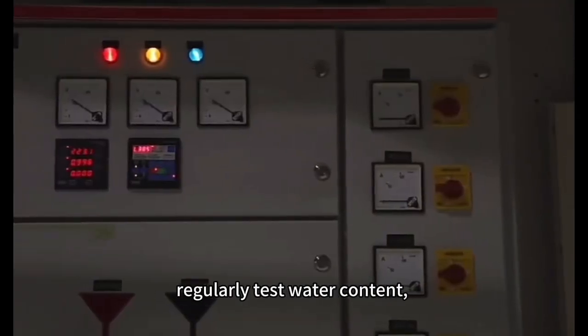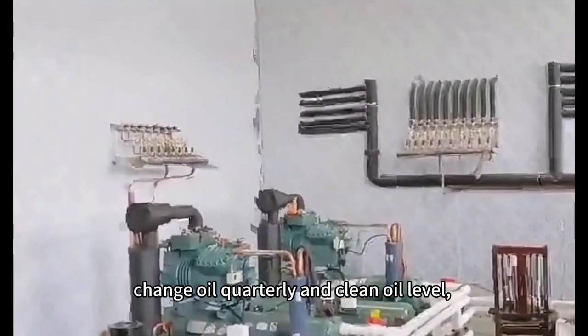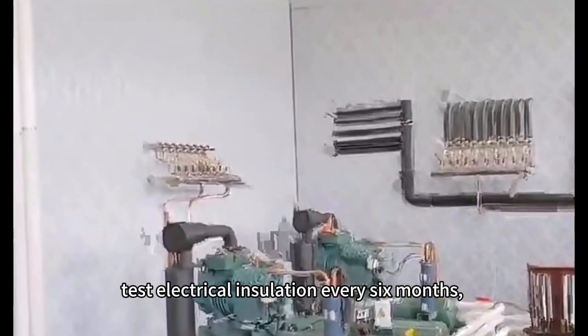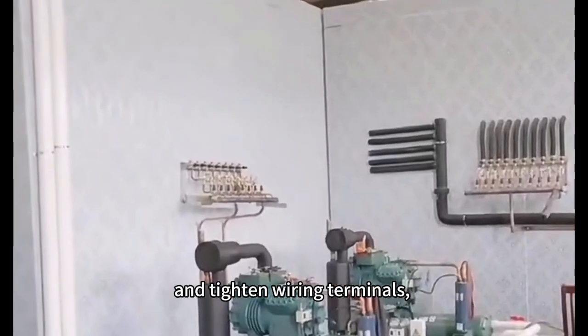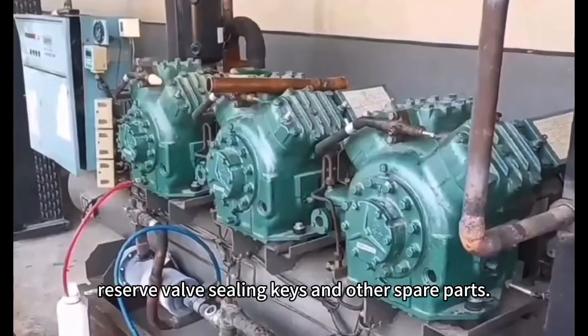Regularly test water content. Change oil quarterly and check the oil level. Test electrical insulation every 6 months, and tighten wiring terminals. Reserve valve sealing keys and other spare parts.